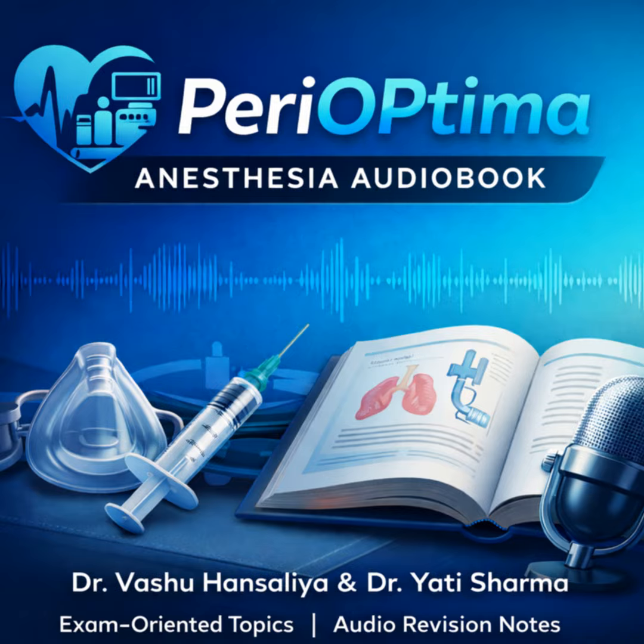This is the next essential system after A, and it represents the flip in efficiency. Correct. The Mapleson D arrangement is optimized for controlled ventilation. The arrangement is the FGI is close to the patient, and the bag and APL valve are remote at the far end of a long expiratory tubing. Which makes it highly efficient for controlled ventilation.